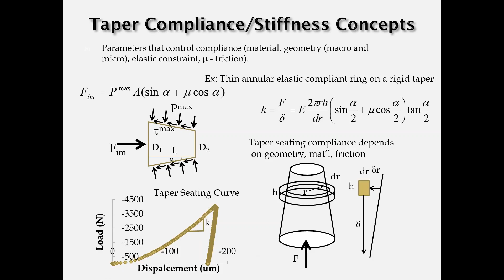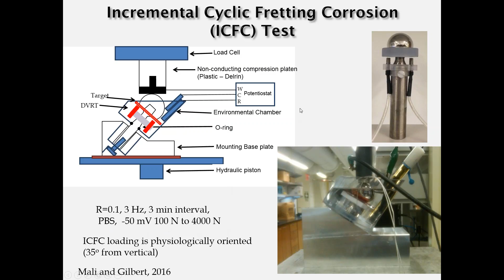This particular test, called an incremental cyclic fretting corrosion test, helps assess materials, designs, or local geometry effects on the fretting corrosion of modular junctions by applying a cyclic load, 3 hertz, 3-minute intervals, in phosphate buffer with the sample held at -50 millivolts, going from 100 newtons to 4,000 newtons incrementally, and measuring the response both electrochemically and in terms of the motion of the head onto the neck. This work has just recently been accepted for publication and will come out in 2016.